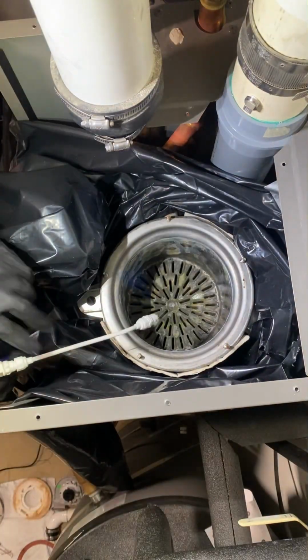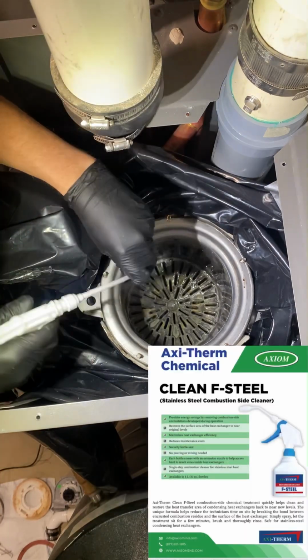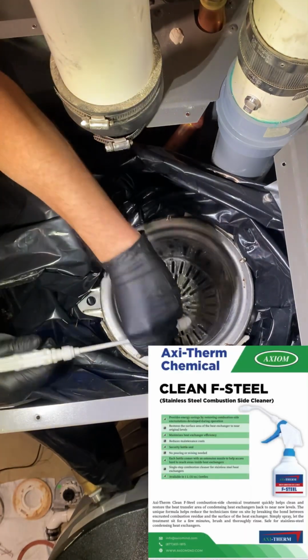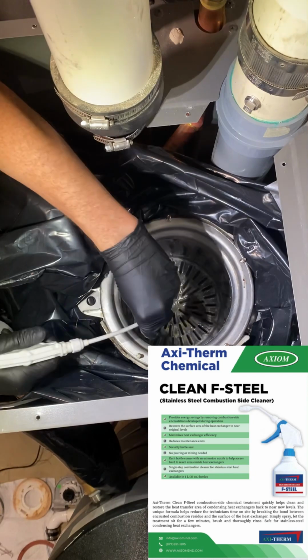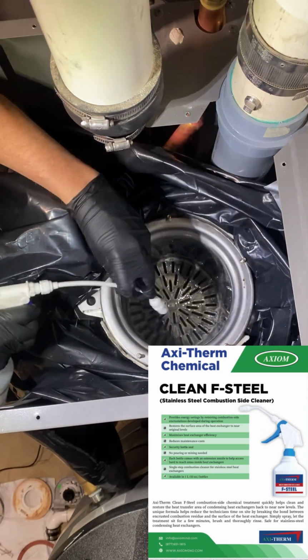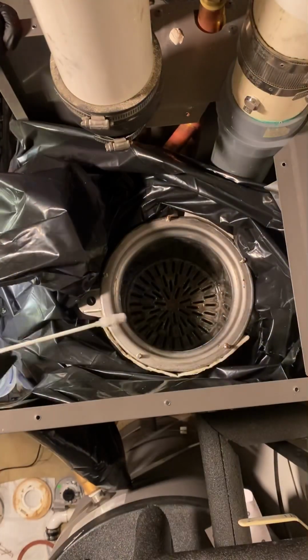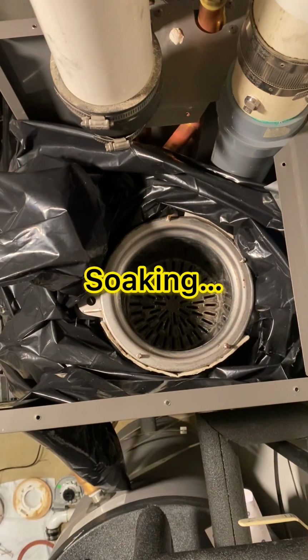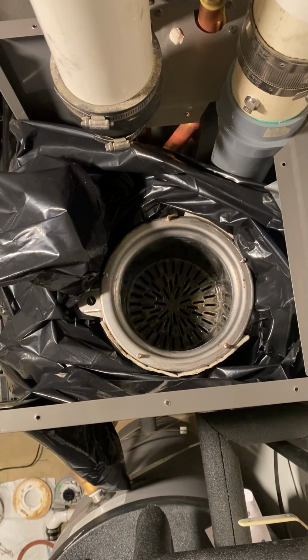Then soak the entire combustion chamber with a stainless steel cleaner like the one shown in this picture. This is some nasty stuff that will choke you out with one whiff, so I like to use the OSHA approved method of holding my breath while spraying. The longer you let it soak, the easier it will be to clean. Oh yeah, you want to make sure the boiler is cold for this step, otherwise the cleaner starts to gum up and will not work well.